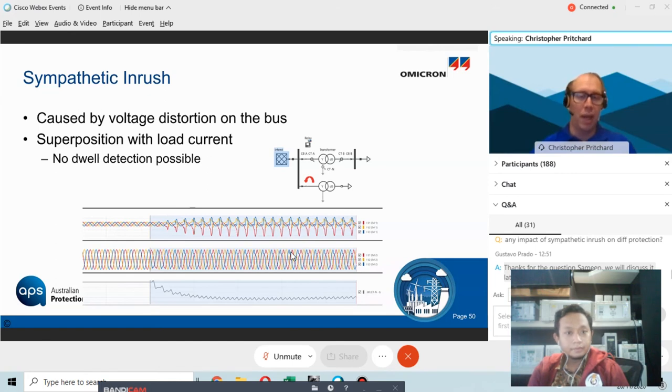is joined by the load current, because our transformer was already energized previously to the parallel transformer. And so this is often a challenge for relays to have the right sensitivity for this inrush current as it's slowly only growing. But again, for testing from system perspective, very straightforward. You have two transformers with the inrush simulation activated, and you close the breaker, and voila, you have sympathetic inrush.